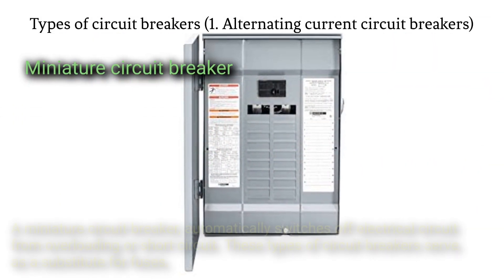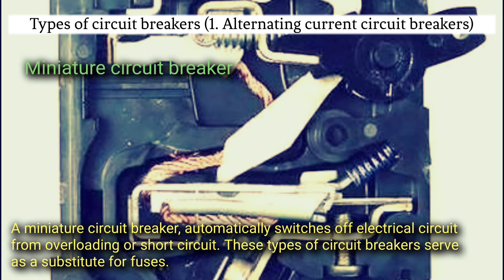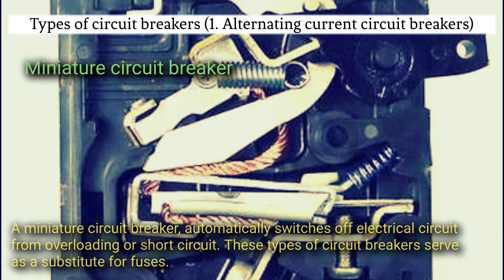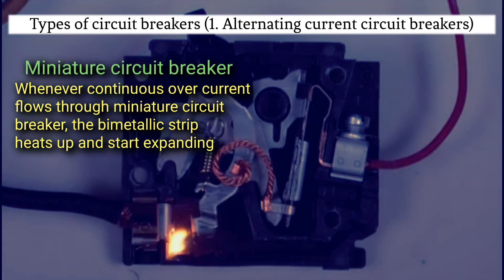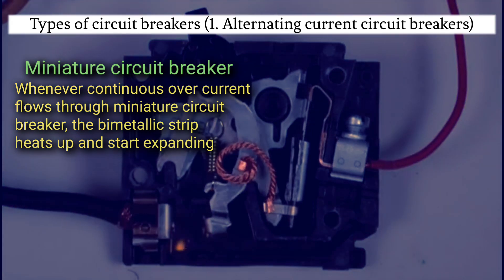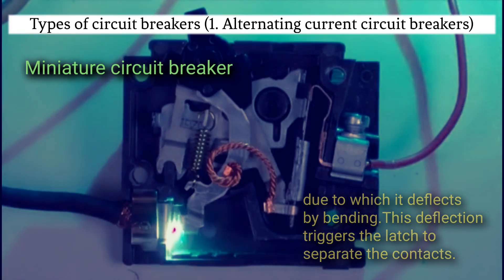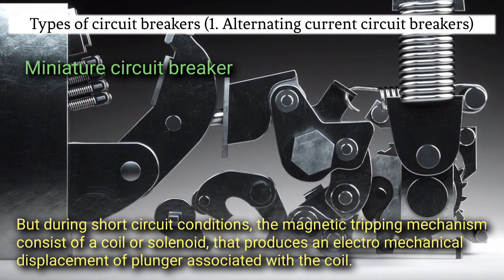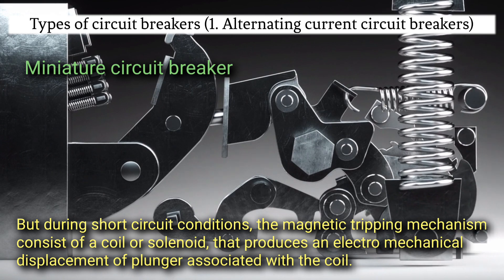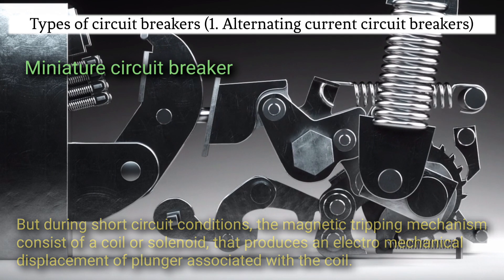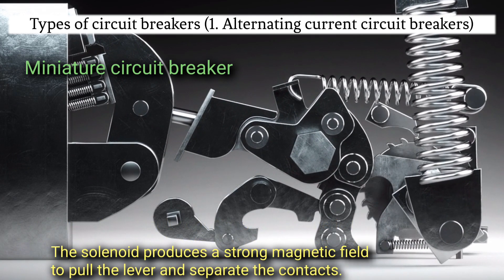Miniature circuit breaker. A miniature circuit breaker automatically switches off the electrical circuit from overloading or short circuit. This type of circuit breaker serves as a substitute for a fuse. Whenever continuous over current flows through a miniature circuit breaker, the bimetallic strip heats up and starts expanding, due to which it deflects by bending. This deflection triggers the latch to separate the contacts. But during short circuit conditions, the magnetic tripping mechanism consists of a coil or solenoid that produces an electromechanical displacement of a plunger associated with the coil. The solenoid produces a strong magnetic field to pull the lever and separate the contacts.